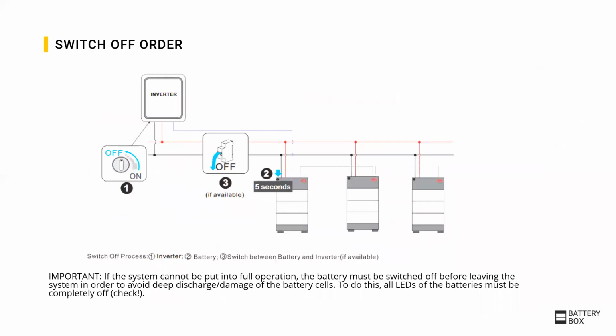For switching off the system, it is exactly the other way around than switching on. First the inverter, then the battery. To switch off the battery, the LED button should be pressed for 5 seconds. Then the system switch will fall automatically.